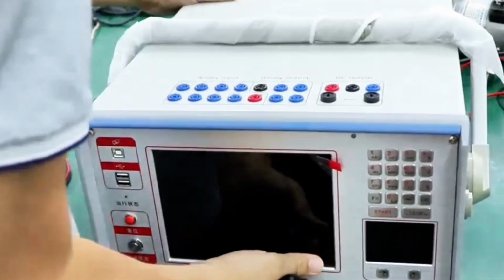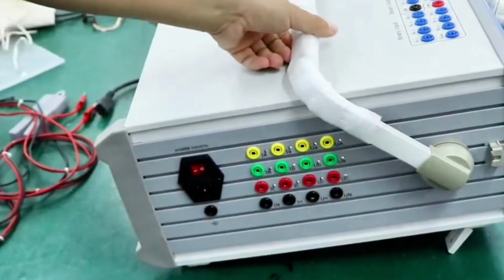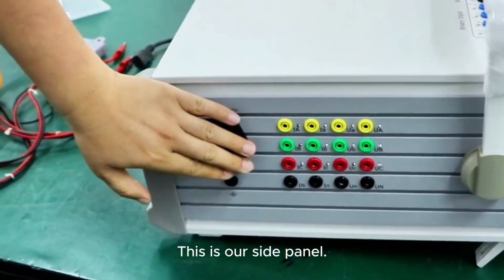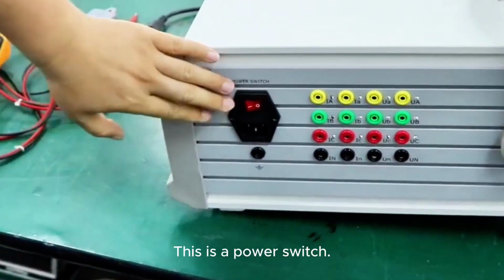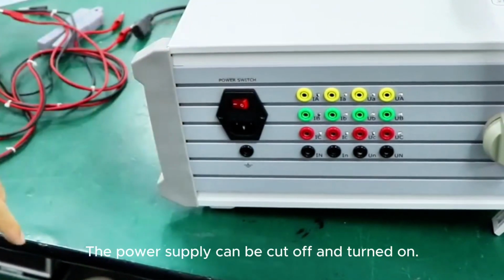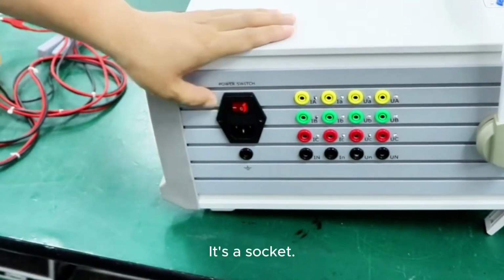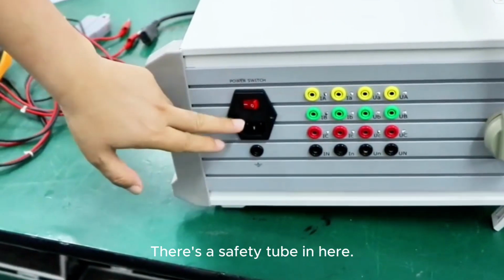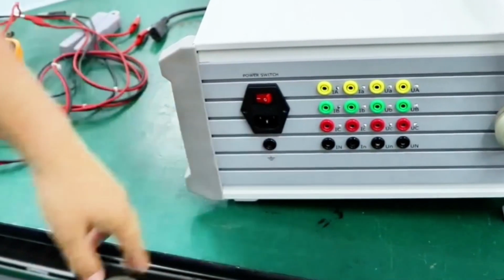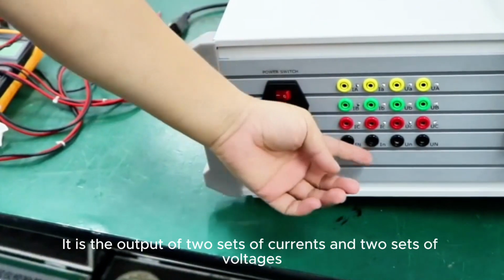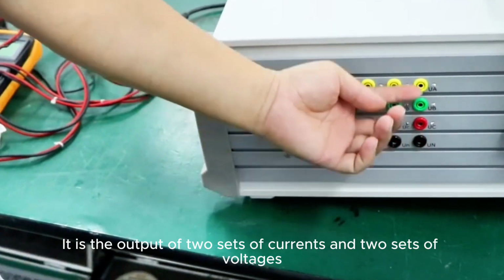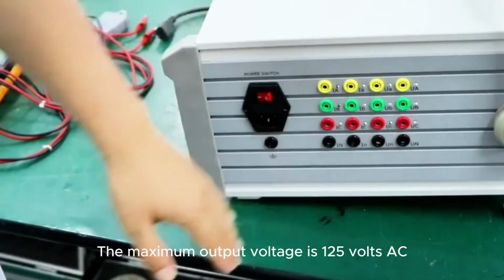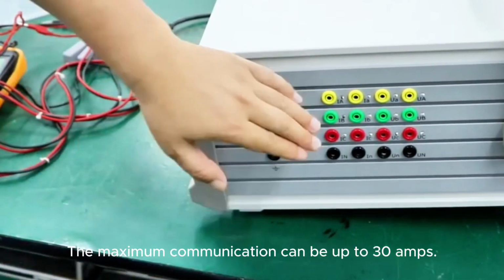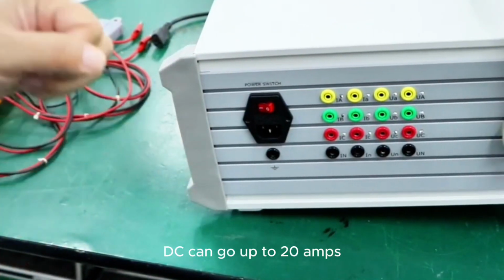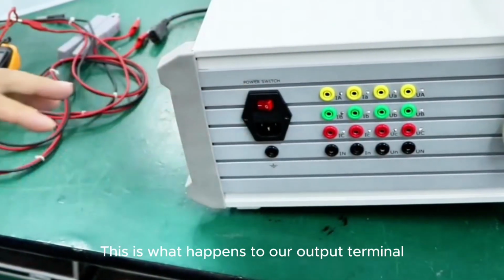Let's look at the side. This is our side panel. This is a power switch. The power supply can be cut off and turned on. It's a socket. There's a safety tube in here. Below is the ground terminal. This way, it is the output of 2 sets of currents and 2 sets of voltages. The maximum output voltage is 125 volts AC. DC can go to 150 volts. The maximum AC current can be up to 30 amps. DC can go up to 20 amps. This is our output terminal.